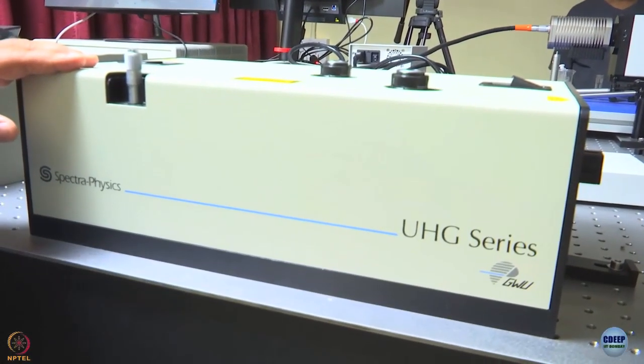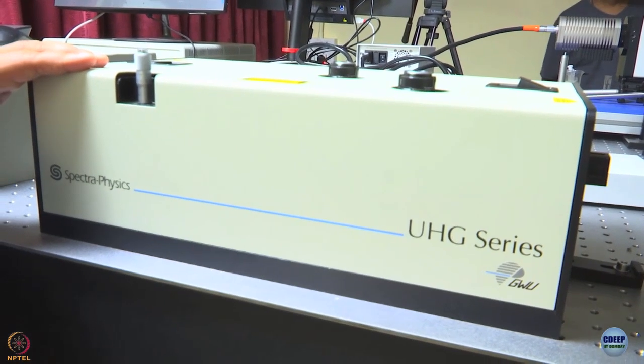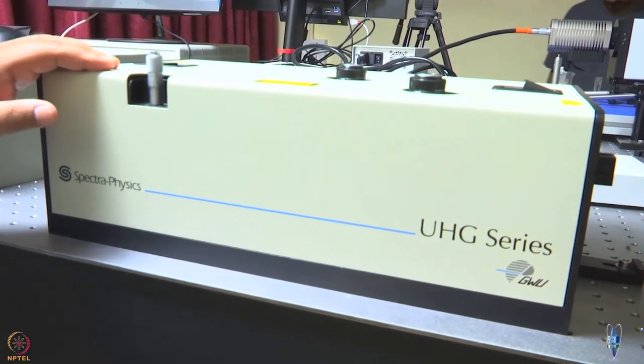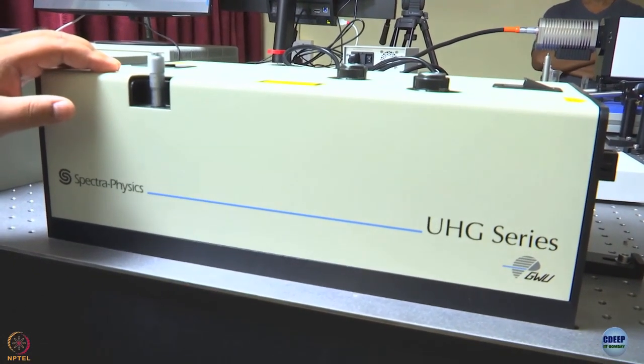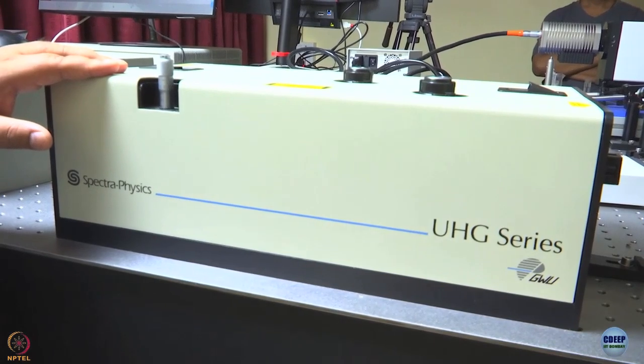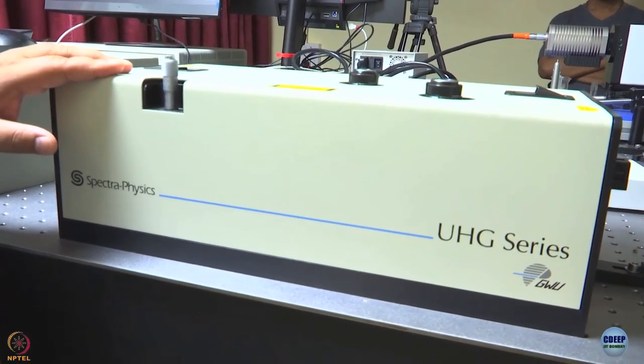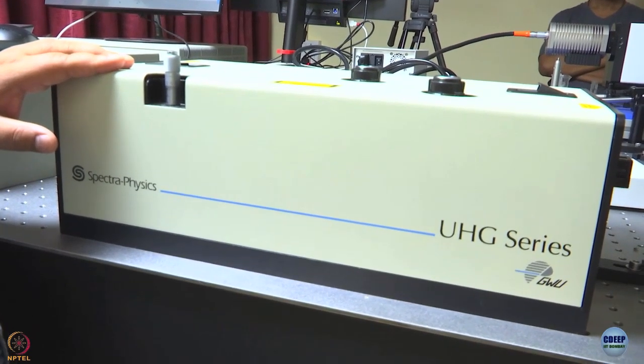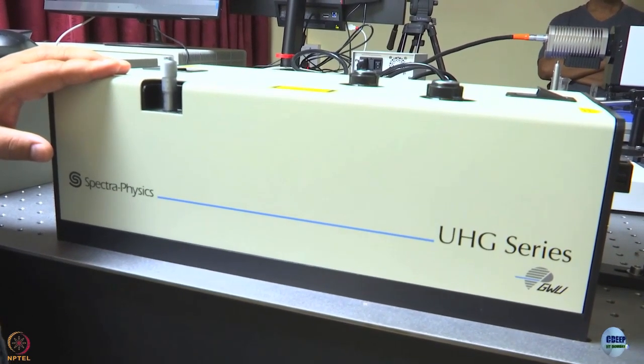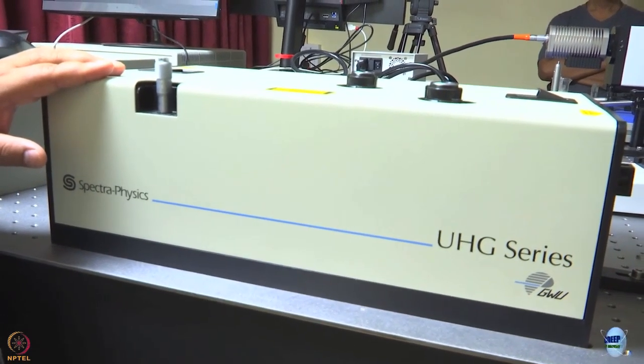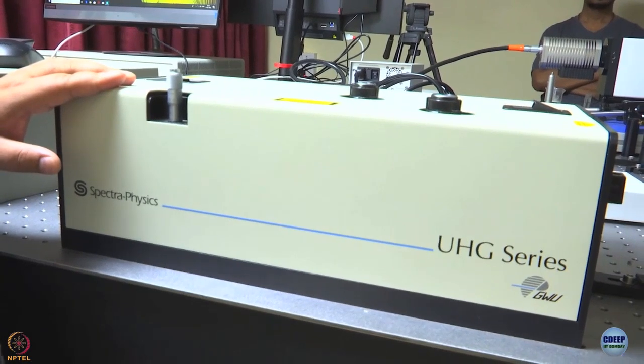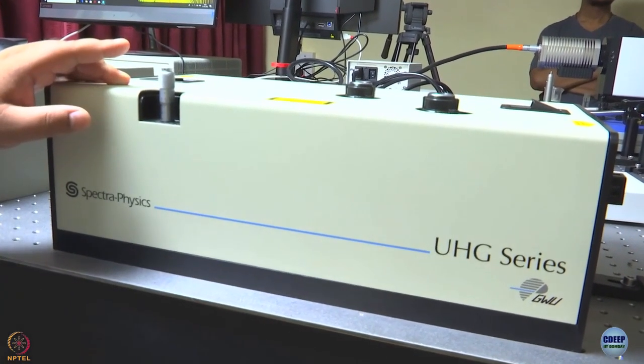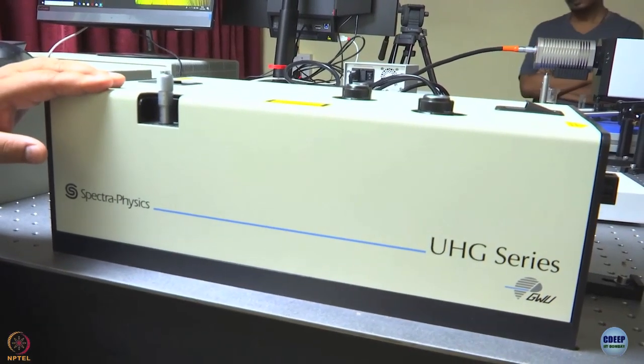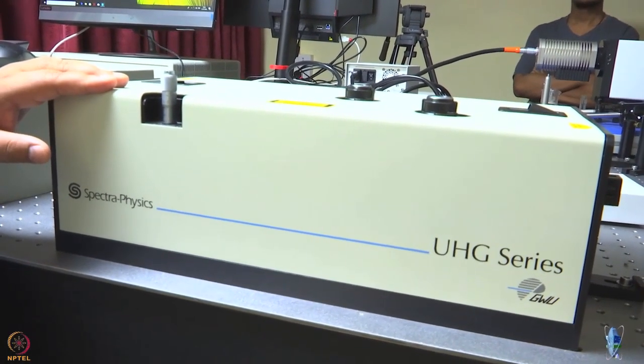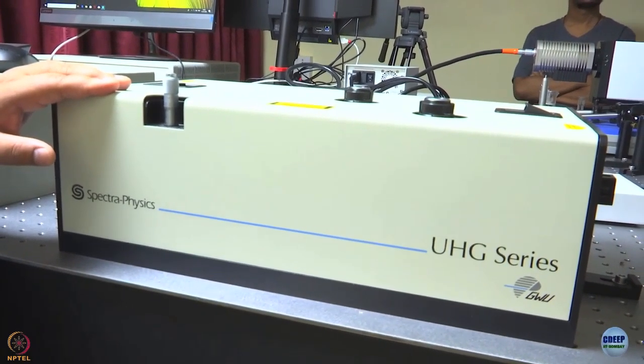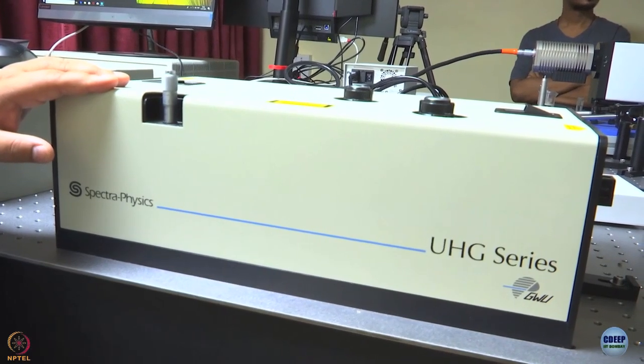Now, the titanium sapphire laser gives us output, as I said, in the range of 690 nanometer to 1040 nanometer, which is basically red, almost near IR kind of range. This wavelength is not really useful for excitation if you are going to talk about a fluorescence experiment. Secondly, the repetition rate at which the pulses come out of the laser is about 80 megahertz or 100 megahertz, you can think, which means the separation in time between two pulses is about 12.5 nanosecond. And that is a problem because if you have a long decay which does not get over in 12.5 nanosecond, then we cannot really record it.